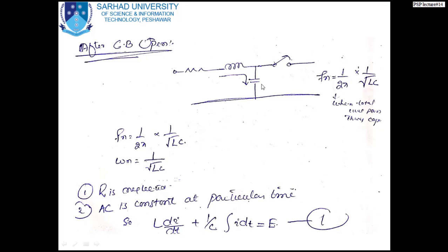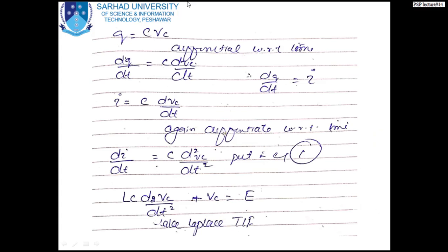And sometimes this voltage rises to a very high value, and that voltage we call the restriking voltage. If the restriking voltage is very high, it may of course break the insulation between the two contacts, and the current or the arc may continue for another half cycle. Okay.